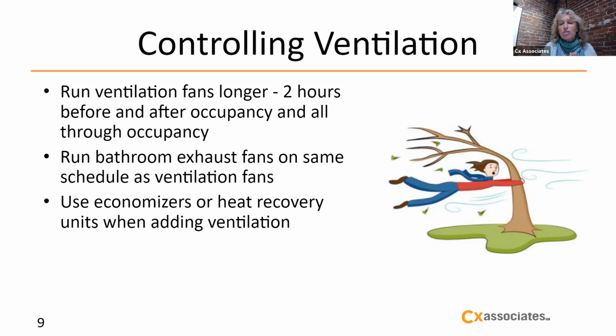There are many ventilation units where the fan is controlled on temperature. So when you've hit the right heating set point or cooling set point, the fan will turn off. You want to make sure that doesn't happen during your occupied hours. You want that fan running all the time. The other thing they recommend is to run the bathroom exhaust fans on that same schedule, so that you are always keeping the building a little bit negative and introducing a little bit more ventilation through your nooks and crannies in the building.